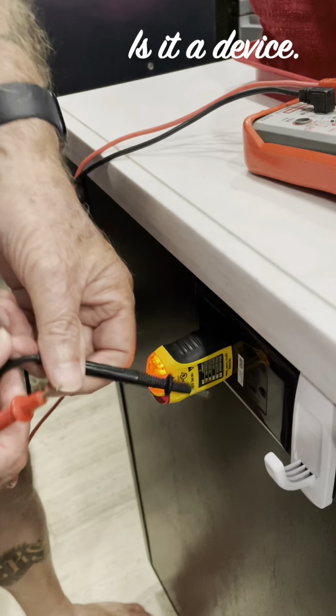A partial failure is usually one of three things. Could be your GFCI circuit, a tripped breaker for a single circuit, or one leg of your 50 amp service is missing. If the things that are not working are only plugged into outlets, it could be a tripped circuit breaker or the GFCI outlet is tripped. The easiest and simplest thing to check is a tripped circuit breaker.